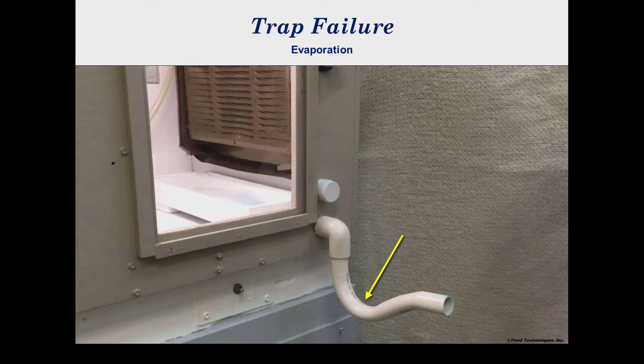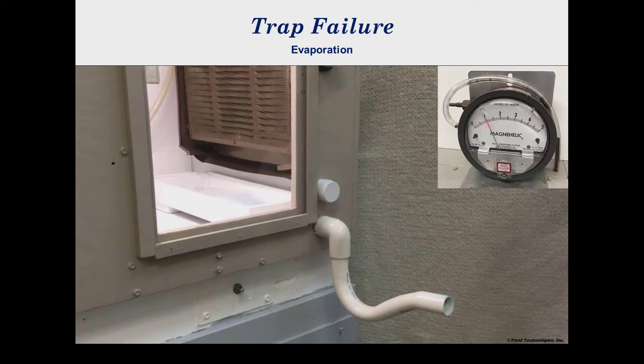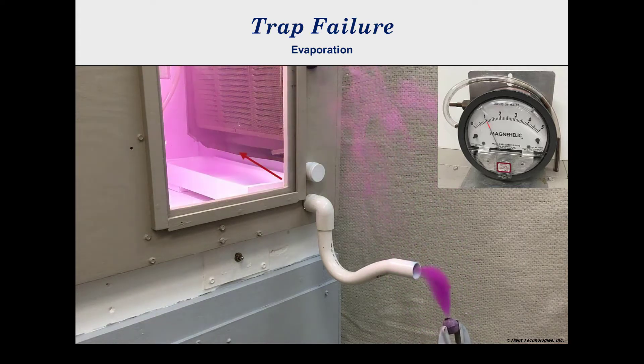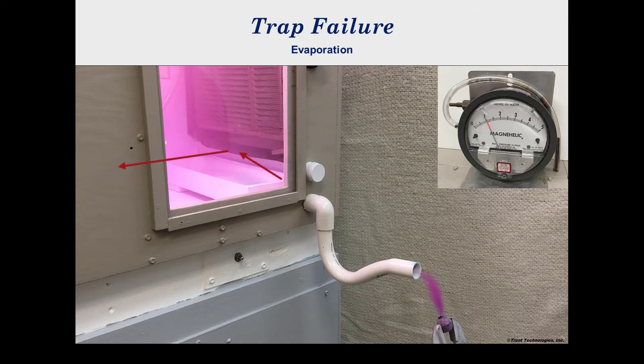The laboratory simulator is being operated with a negative one inch of water pressure. Systems are often operated at this or more negative pressures. During startup after a heating cycle, like for summer cooling, trap water is evaporated, allowing air ingestion. Deflection of the benzene lighter flame shows how contaminated air can be drawn into the unit, and the introduction of smoke near the drain outlet shows how polluted air can be drawn into the system and spread into the conditioned space.